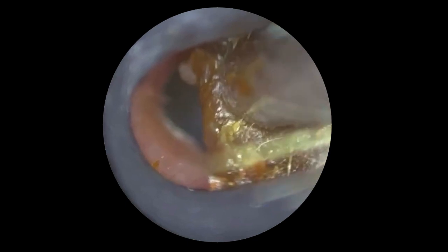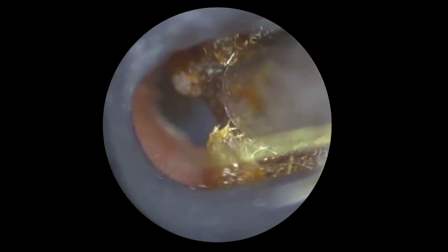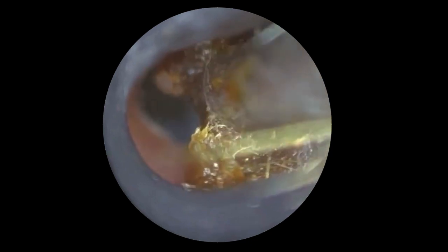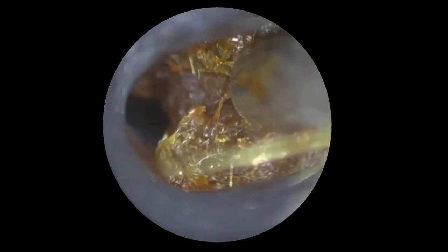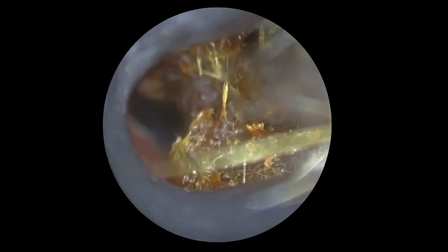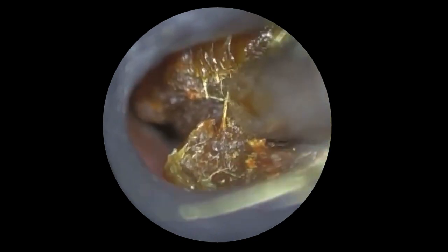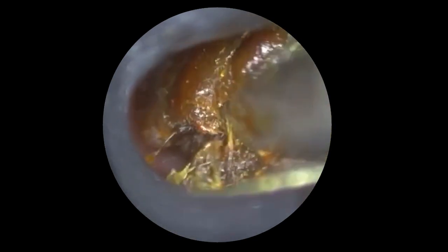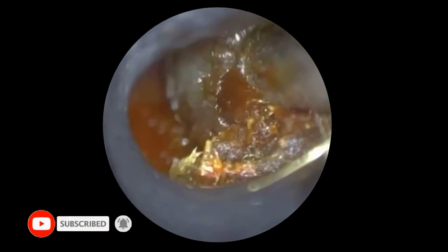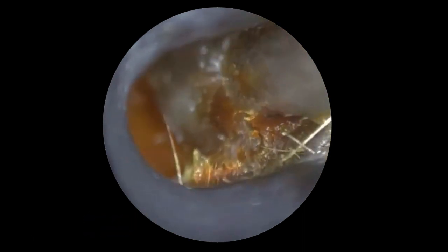Having the slit allows more manipulation of the instrument, and it comes from a higher angle of incidence, so it doesn't get blurry in view. Also, in terms of infection control, the suction probe is only making contact with the speculum. It's not going through any mounting system which the speculum is attached to. So if you imagine you've got a device where you've got a speculum attached to a mounting system, and the mounting system is fixed as part of the device, and you're going in and out of that mounting system, that mounting system is potentially a hazard because of all the bacteria and wax from the previous patient. There's no means of sterilising that.